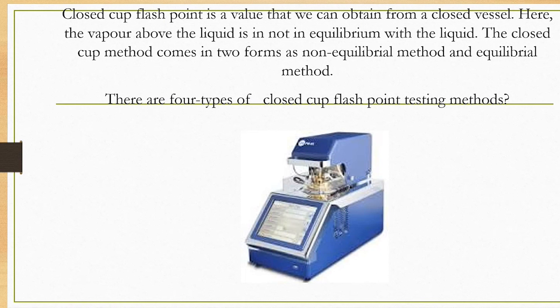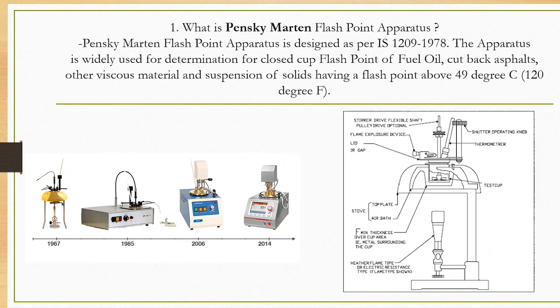Now we are going to cover the closed cup flash point test. In the closed cup method, you conduct the test using a vessel which is sealed from the outside atmosphere. You heat both the vessel and sample, which replicates the effect of accidentally introducing an ignition source into a sealed container, such as a gas tank or other storage vessel.